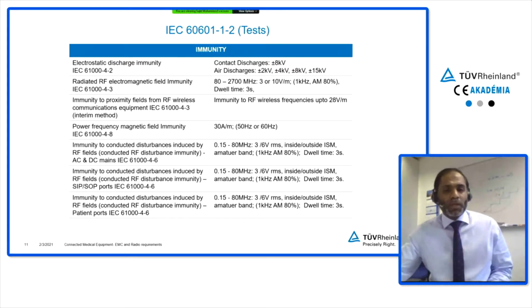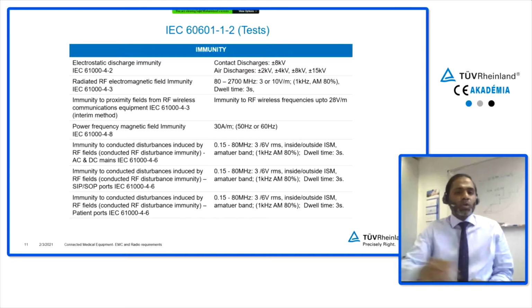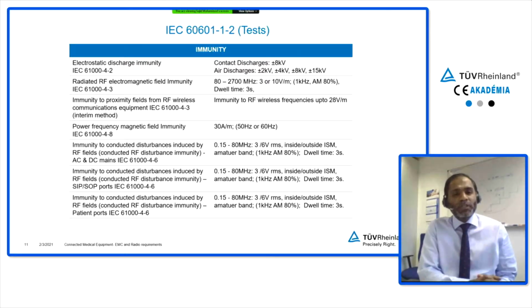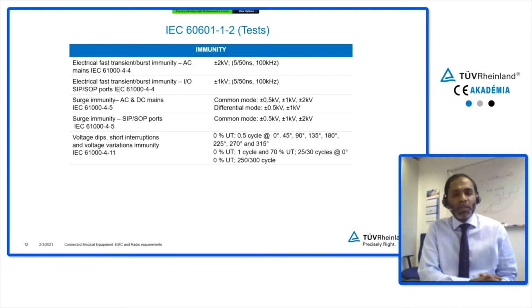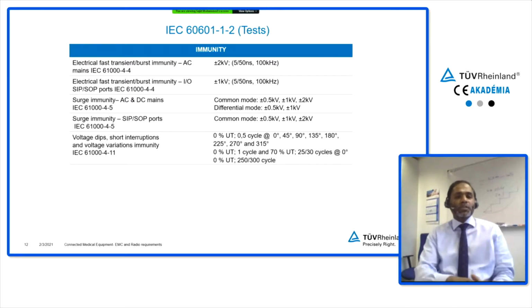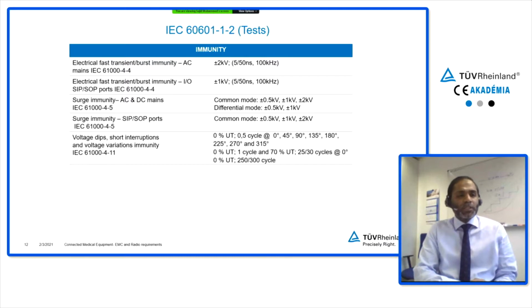This is followed by some more tests: electrical fast transients and burst immunity testing according to IEC 61000-4-4, plus or minus 2 kV, and transients on the signaling ports, signal input ports, signal output ports, and surge immunity tests for AC and DC, as well as for signal input ports and signal output ports, followed by voltage dips, short interruptions, and voltage variations immunity.